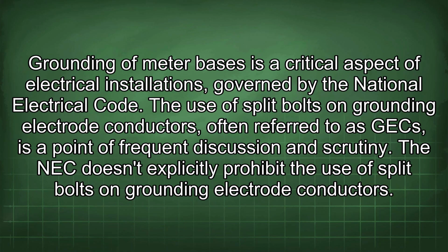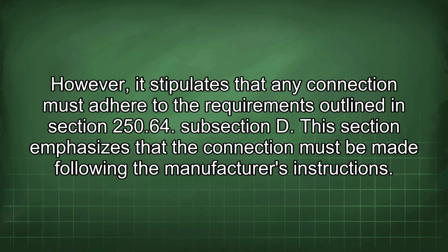Grounding of meter bases is a critical aspect of electrical installations governed by the National Electrical Code. The use of split bolts on grounding electrode conductors, often referred to as GEC, is a point of frequent discussion and scrutiny. The NEC doesn't explicitly prohibit the use of split bolts on grounding electrode conductors. However, it stipulates that any connection must adhere to the requirements outlined in Section 250.64. Subsection D. This section emphasizes that the connection must be made following the manufacturer's instructions.